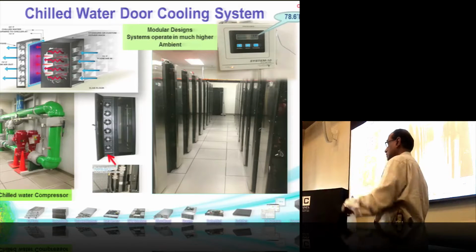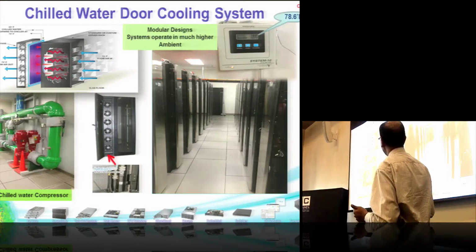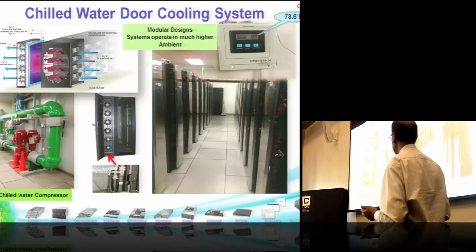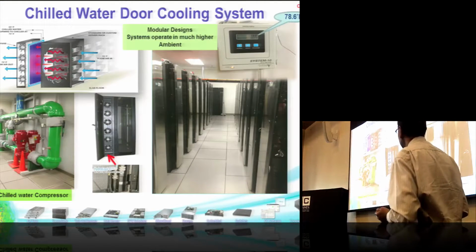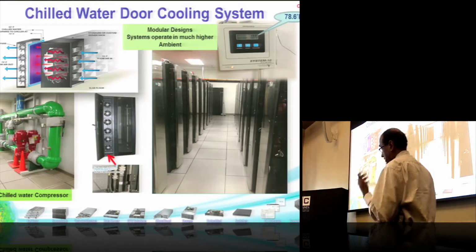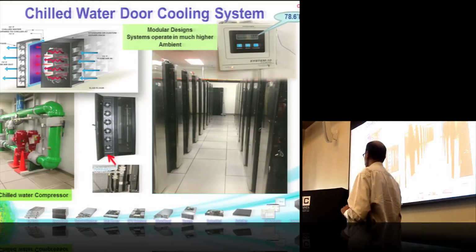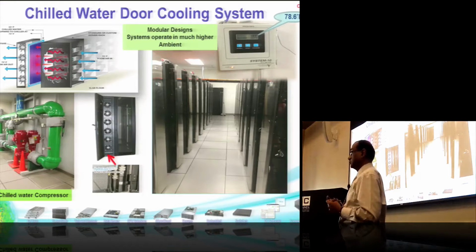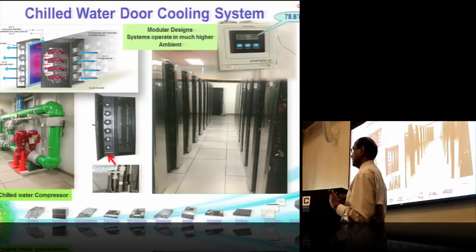So you're capturing most of it. You have airflow from the front to the rear, and then the chilled door blocks or captures the hot air, which feeds back into the chilled water compressor system. From an economics perspective, this is by far the cheapest and easiest to implement. They've claimed they can actually do a retrofit within a day.